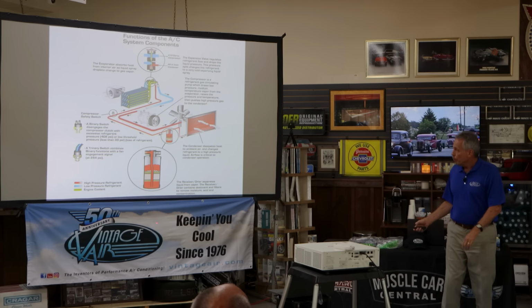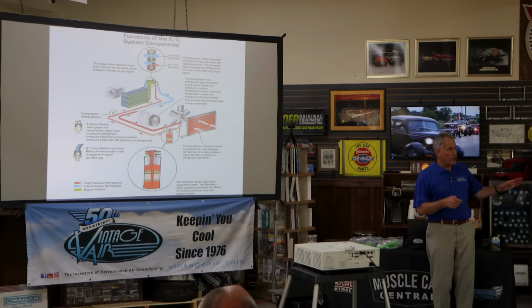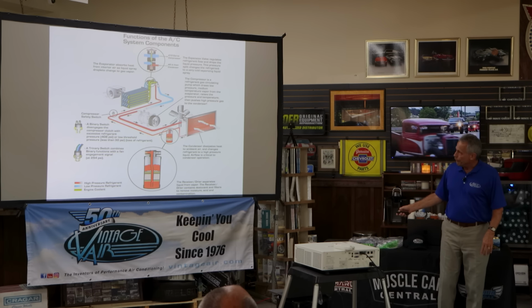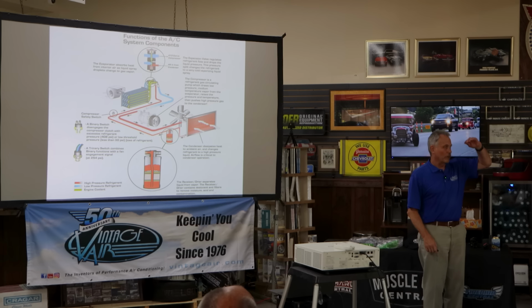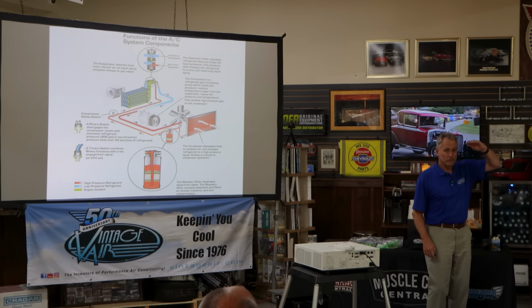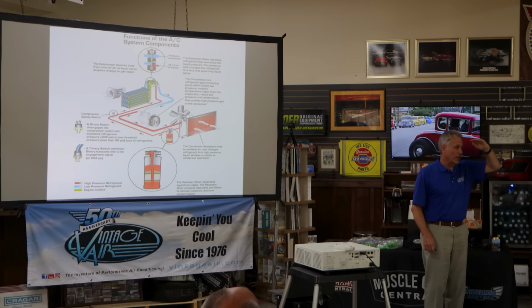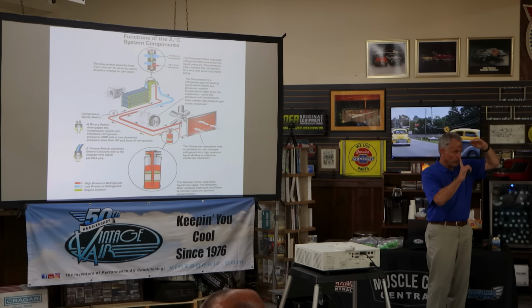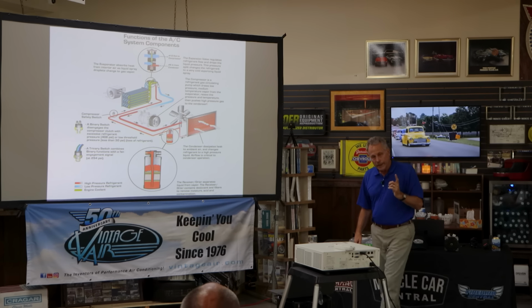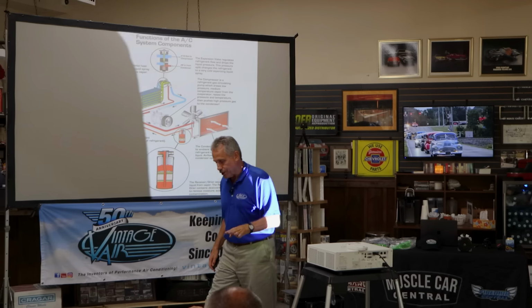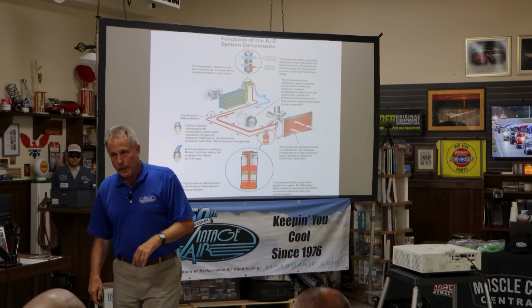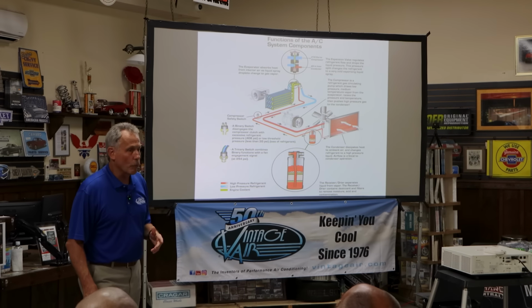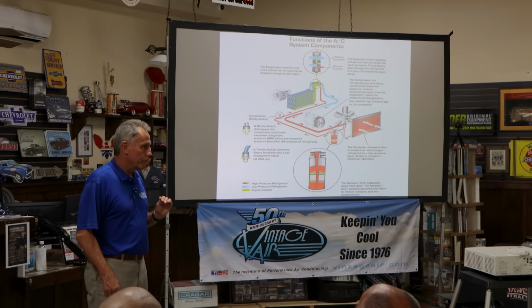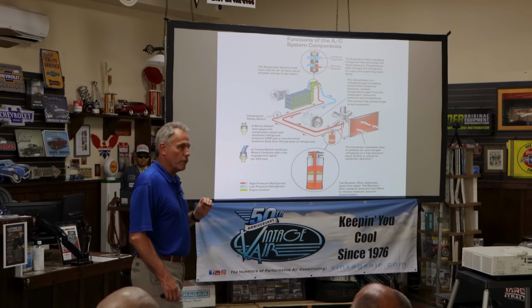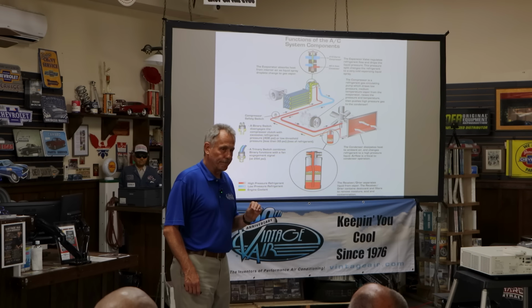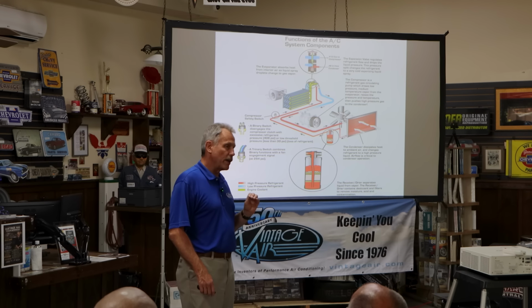So the bubbles you see are oil. So if you put in refrigerant till there's no bubbles, what you've done is you've filled that dryer completely full of liquid refrigerant. Bubbles go away because it's all liquid at that point, but you got too much refrigerant. You get poor system performance. One of the biggest issues with system performance on any system with 134A, and even more so with the new 1234YF, is charge. When you're using 134A refrigerant, you have to use the right amount. It isn't a guess.